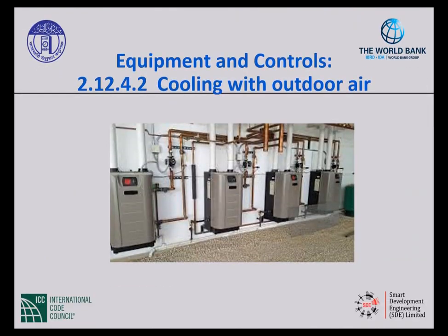All right, equipment and controls. So sections 2.12.4.1 and 2.12.4.2 talk about air conditioning, heating, and ventilation systems shall be equipped with devices and controls to automatically control the capacity of the system when the building requirement reduces. Okay, so this is telling us that the control system has a device to reduce energy use considering the effective building energy storage. So looking at part load controls and sequence of operation.